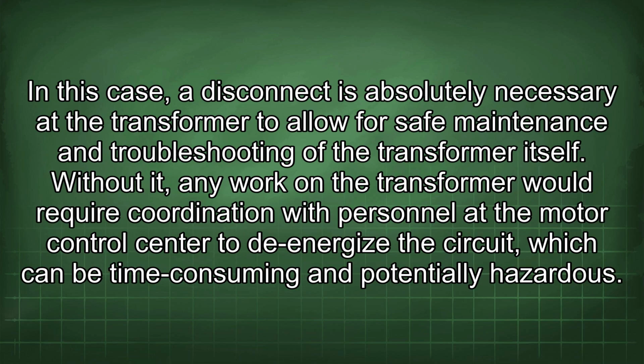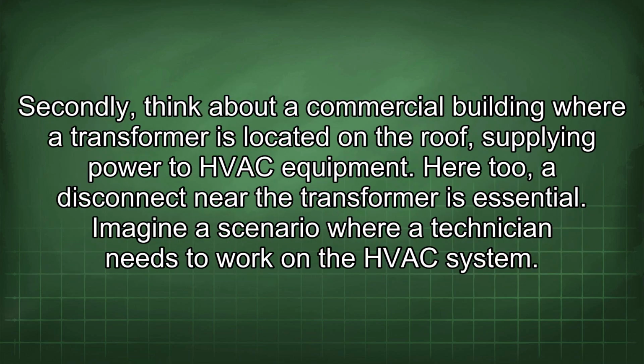In this case, a disconnect is absolutely necessary at the transformer to allow for safe maintenance and troubleshooting of the transformer itself. Without it, any work on the transformer would require coordination with personnel at the motor control center to de-energize the circuit, which can be time-consuming and potentially hazardous. Secondly, think about a commercial building where a transformer is located on the roof, supplying power to HVAC equipment. Here too, a disconnect near the transformer is essential.